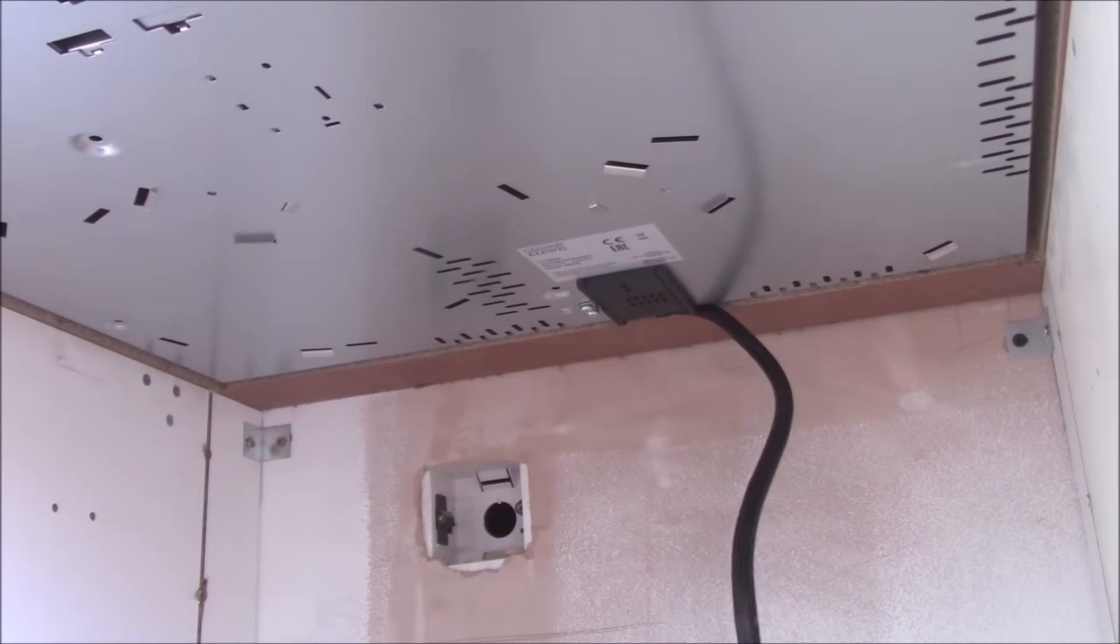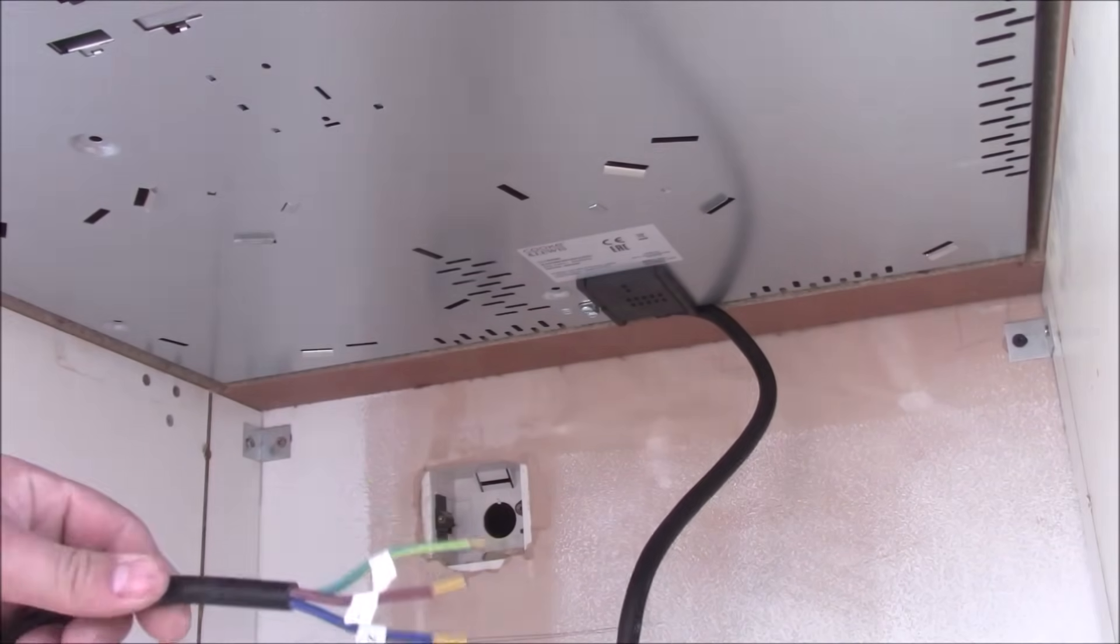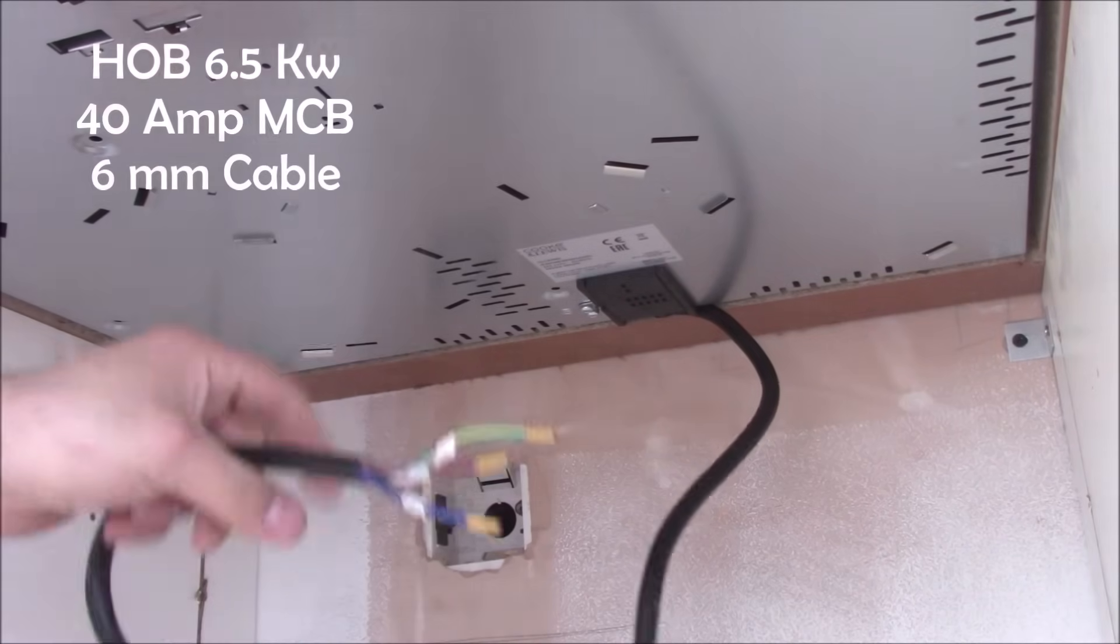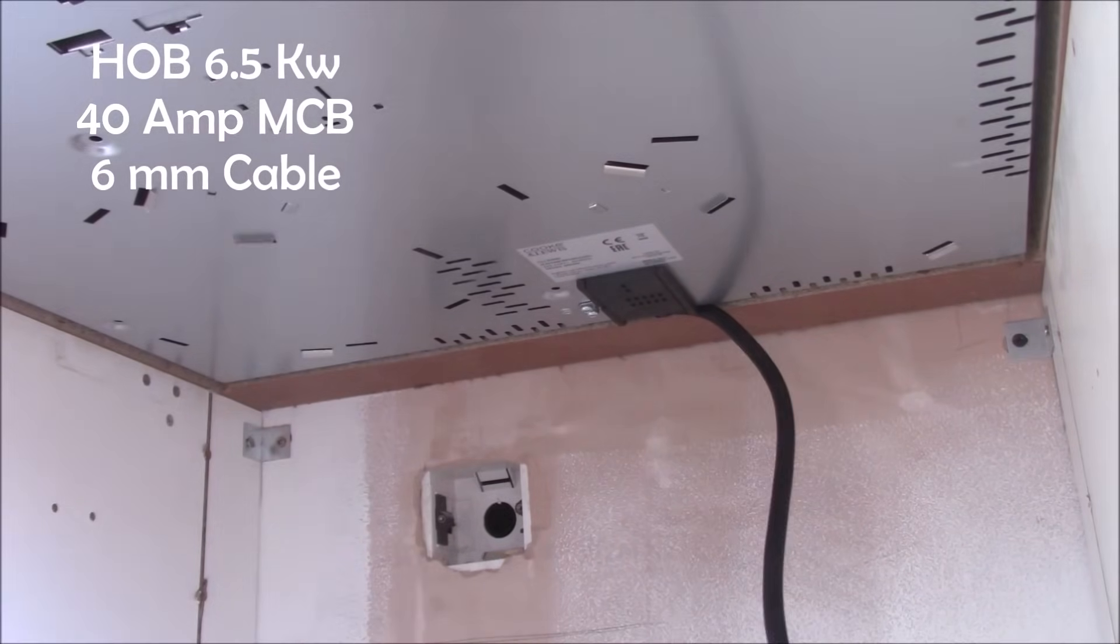So now let's do the wiring. You see the thick cable. This hob is 6.5 kilowatts, so you need at the consumer unit you need 40 amp MCB and 6mm cable going straight up to the switch and from the switch up to here.